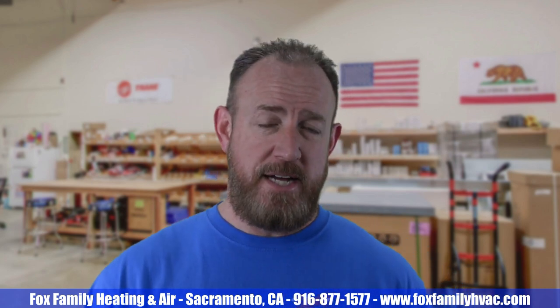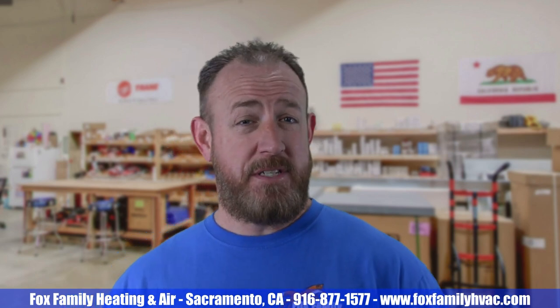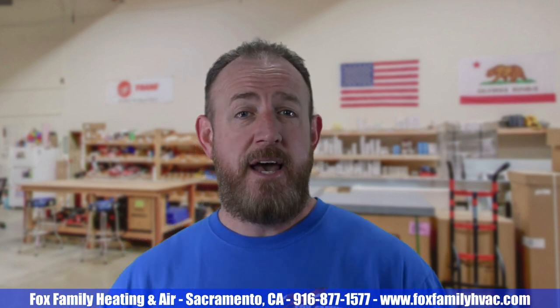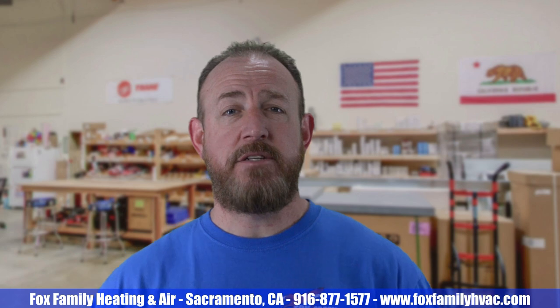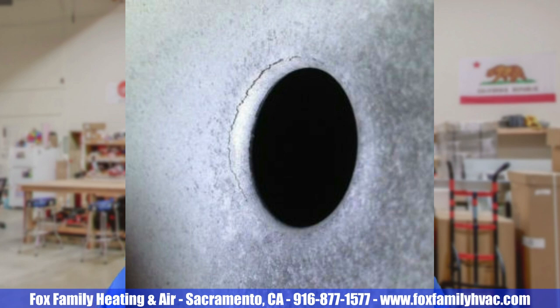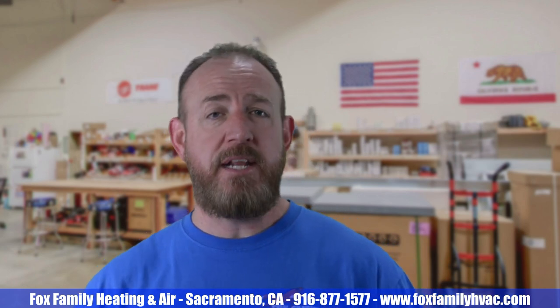Poor Manufacturing Design. There are clamshell, serpentine, and tubular heat exchanger designs. Clamshells tend to fail in the back of the chamber, but it's tough to get an inspection mirror back there. A process called HydroScan is used to identify cracks in these types of heat exchangers, and it's very effective if done right and if the professional is looking in the right spots — it definitely takes a trained eye. Serpentine designs are pressed together with the middle areas held together with rings or eyelets. The eyelets on serpentine designs tend to deform, pop off, and crack. If the manufacturer wouldn't send a heat exchanger out with cracked or missing eyelets, a technician who later finds them like that should fail your heat exchanger for not meeting manufacturer specs.